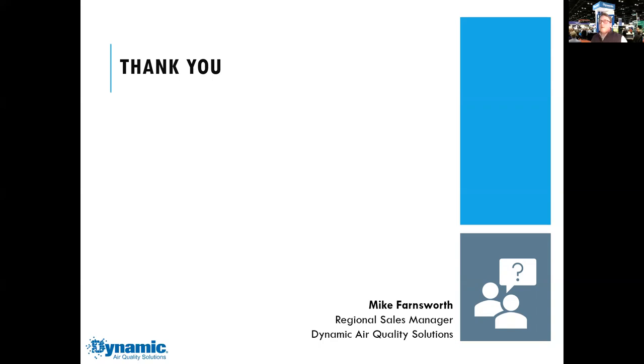Right. Yeah, Dynamic has a range of products. The V8, for example, is what we tend to use in our larger commercial applications. And that product does have a MERV 13 as well as a MERV 14 rating, which we use for healthcare. Some of our, what we call glass media products that we sell in 1 and 2 inch panel types have a MERV equivalency. And that equivalency is based on recirculated air. And so I'm not sure if everybody's familiar with the equivalency, but it's essentially the appendix of the ASHRAE 52.2 that says if you can remove indoor particle counts to the equivalency of what a MERV 13 would have removed on the first pass equivalent, it's equivalent.